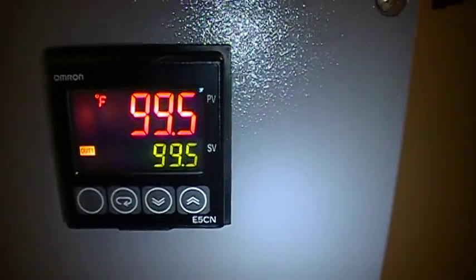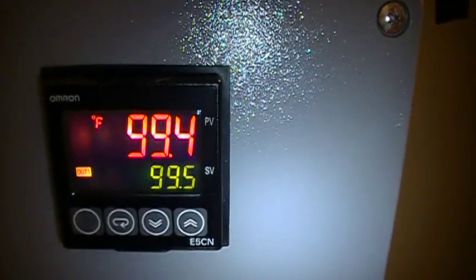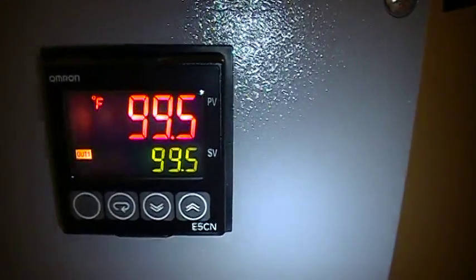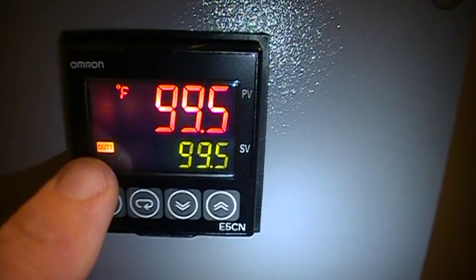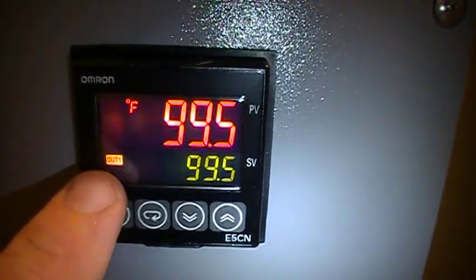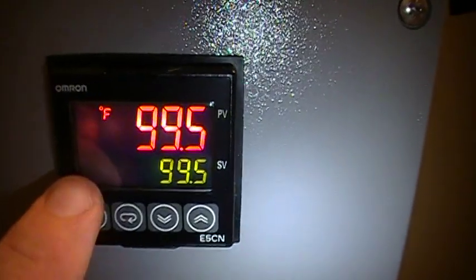You can see that I have my high limit alarm set at 100.5, so that if it gets that temperature or above, I'll get a piezo alarm letting me know that it's too warm. If it gets down below 98, I'll know that it's too cool in the incubator. If you'll notice the temperature, the bottom in the green is my set point. I have it set at 99.5. You can see that the actual temperature right this minute is 99.4. If you'll notice here, this is the light indicating that current is right now being supplied to the heating element. You just saw it go off to keep this at 99.5.